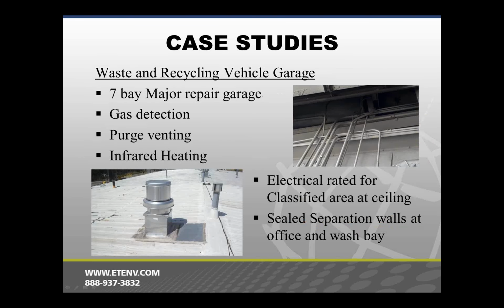Next one, this is a waste hauler outside of Milwaukee. They had a 7-bay major repair garage. They ended up with a full upgrade for a major repair garage, including gas detection, purge venting, brand new heating system, and all the electrical in this building was actually rated for classified areas. It was prior to the state adopting those revisions to the electrical code. And then, again, we had adjacent areas that needed to be sealed up, so we couldn't migrate hazardous vapors.